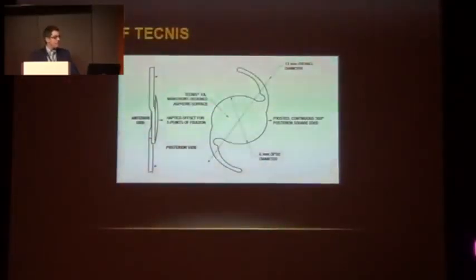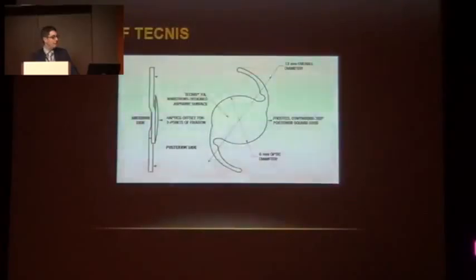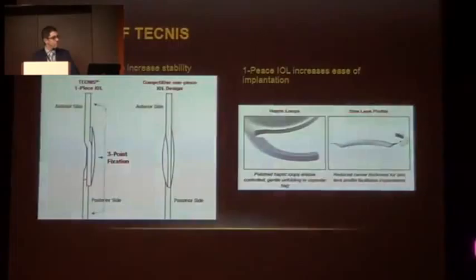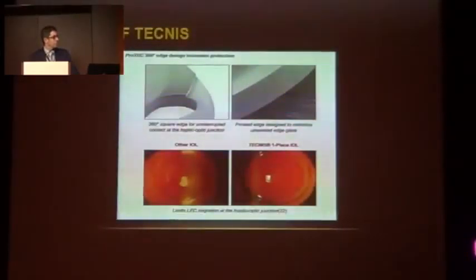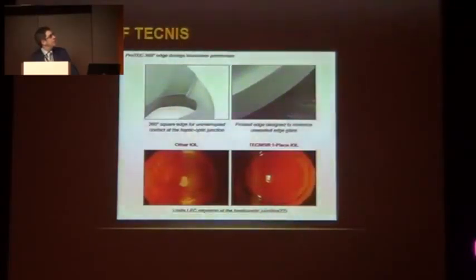The lens design has the diffractive structure on the anterior surface, while the posterior surface is the refractive surface. We can see three points of fixation to increase stability, and the 1-piece IOL increases ease of implantation. The edge design increases protection, and the frosted edge design minimizes unwanted edge glare.